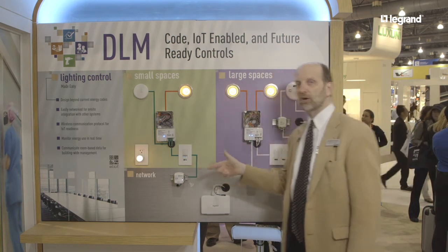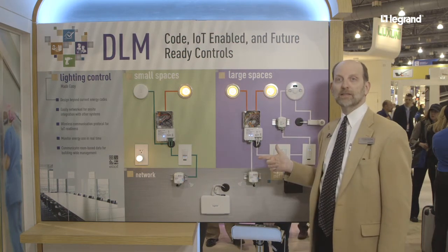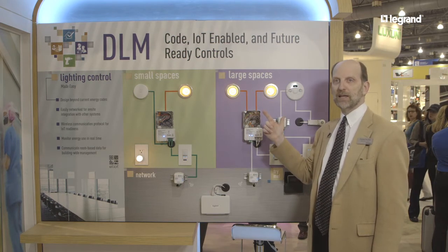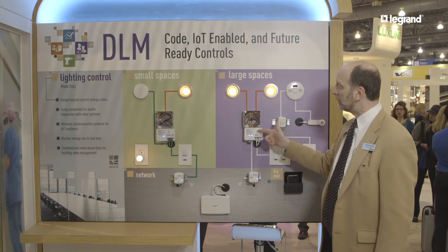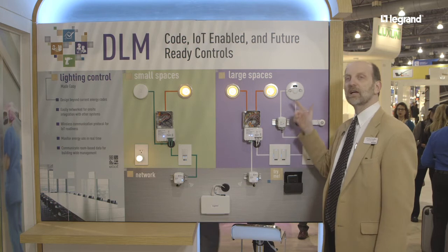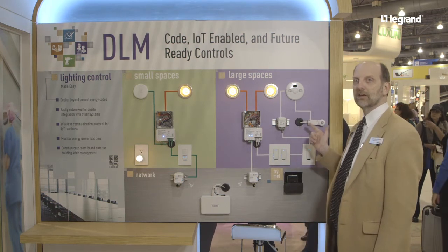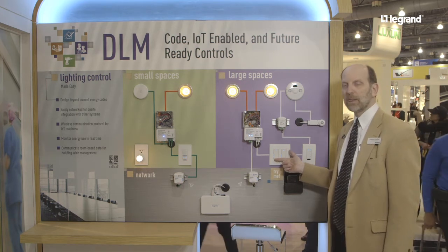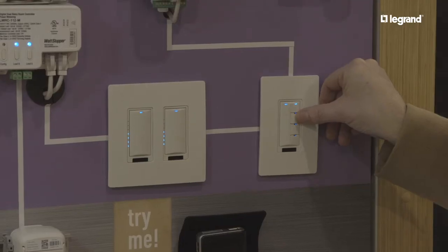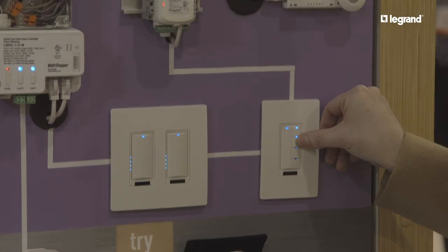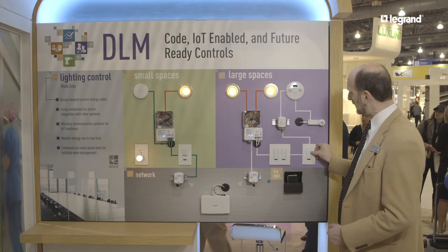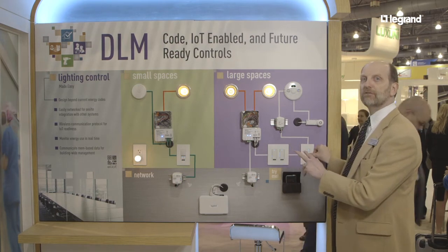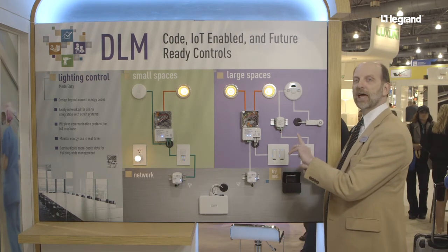So that's a small room, but what we might also have on that same floor is a couple of larger rooms where we have multiple lighting loads in the space. We need the same room controller, but with two relays, a ceiling mount occupancy sensor, a photo cell, and the dimmers to be able to control each of those loads. In addition, we wanted to add a scene switch so that we'd be able to make scene changes.